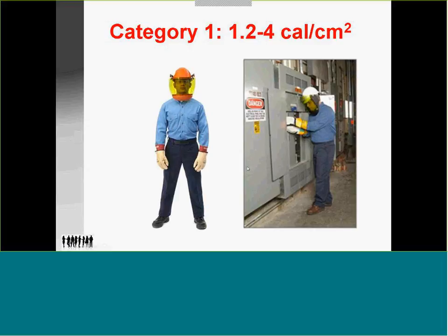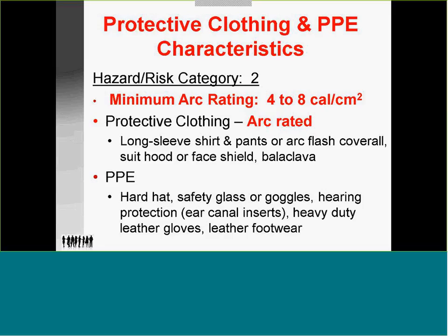As you can see in both photos, this is what a category 1 would be. The clothing is arc rated. Notice the gloves cup over so an explosion cannot go up the inside of the sleeve in working condition. And notice it has a chin guard on here so an explosion will not press the plastic against your face. It will not melt, it will not burn. It may harden and become brittle, but it will hold for the intended use.